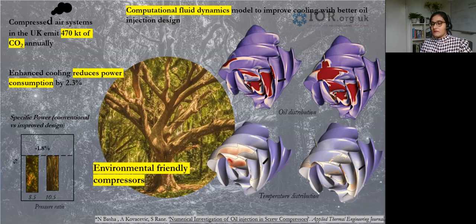If we take the same amount of oil, shown on the right-hand side of the figure, and distribute it evenly, then the oil is well distributed, which reduces the temperature spots in the compression chamber. The difference between the conventional and the improved design is a reduction of 35 to 40 degrees in compression chamber temperature. This reduces power consumption by 2.3%, and more importantly, the specific power is reduced by 1.8%.